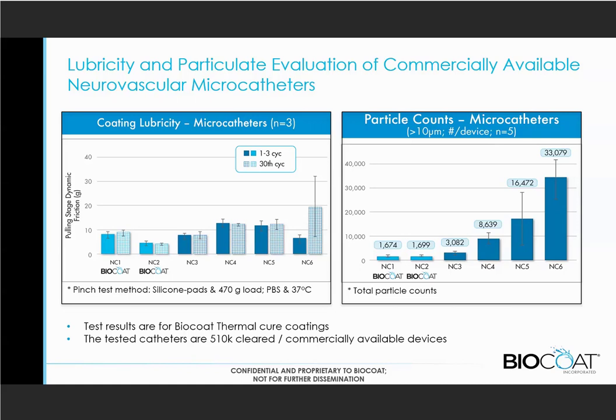The NC6, not surprising since the durability is not as good, probably has a lot more particles. But the other 5 also had a 10x difference in the amount of particles being generated, all with essentially the same lubricity and good durability from the friction testing. And so this helps differentiate between different kinds of coatings. We're admittedly being very aggressive on this, but it shows some of the difference that you see from the coatings and these devices.